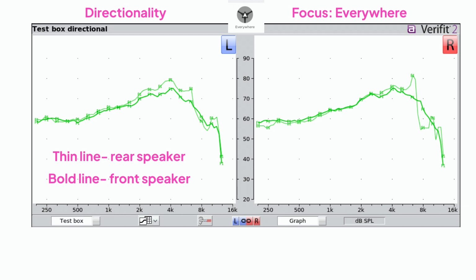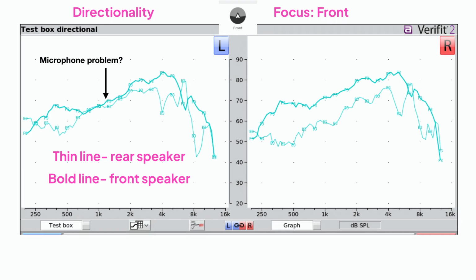Directionality. These graphs essentially show gain for sound coming from the rear speakers in the test box versus gain from speech sound coming from the front speakers. Here you see little difference when the hearing aids are in everywhere mode or omnidirectional versus a difference here of roughly 10 dB when they're in the front focus mode. Like mentioned before, the differences for the left hearing aid were minimal, suggesting a problem with the mics there. But for the right hearing aid, the directionality is pretty impressive.